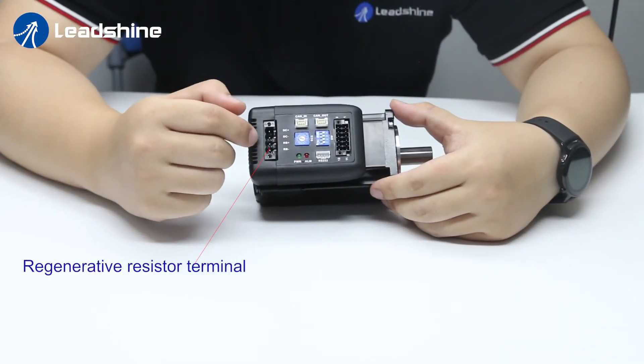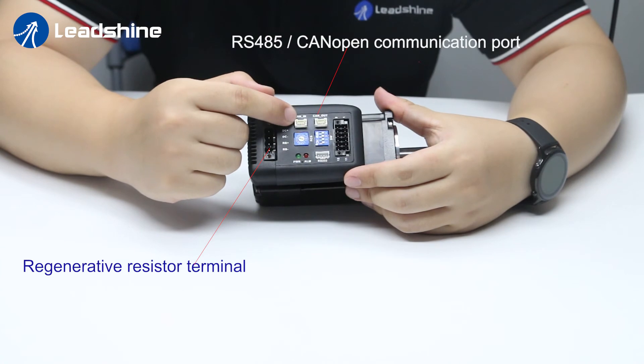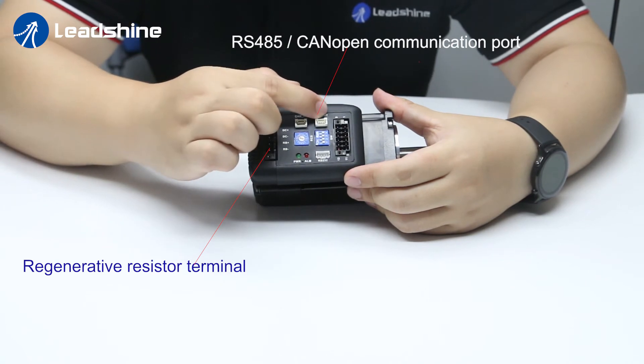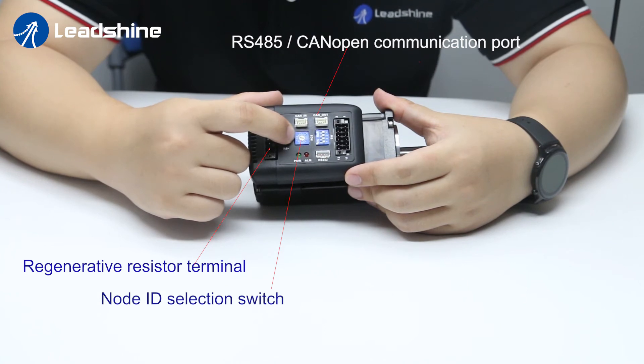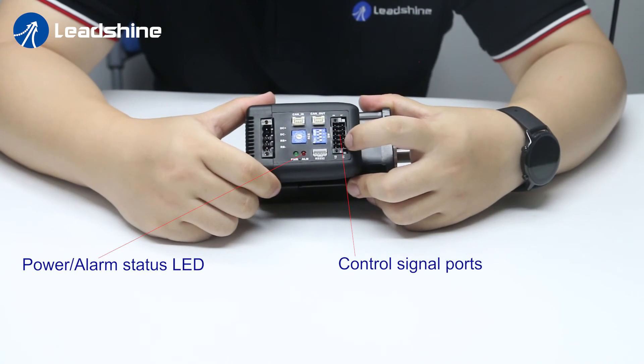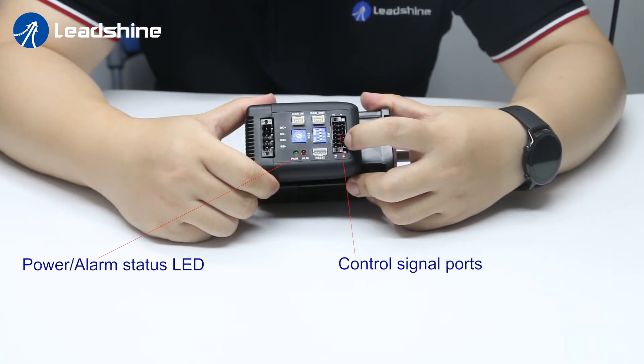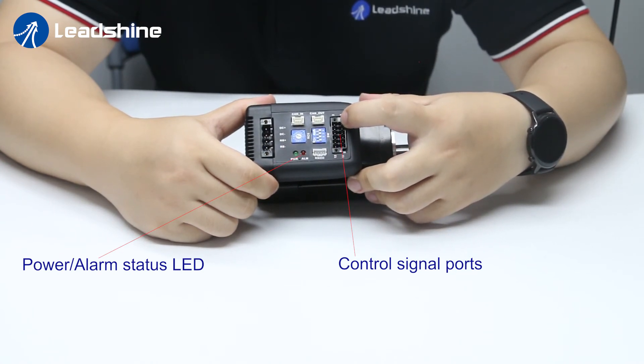As you can see, there is a regenerative resistor terminal on the motor body. There is an RS485 and CANopen communication port on the motor body for signal in and out, as well as a communication node ID selection switch. There is a baud rate and onboard terminal resistor selection switch. There is a power and alarm status LED. There are four programmable digital inputs allowing sink inputs and source inputs, and two programmable digital outputs allowing single-end connection.